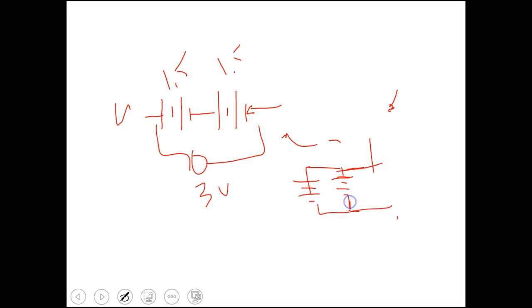Now what's this going to do? It's going to increase the current. So if we hook DC sources - you'll see your remotes do that more often - they'll hook them in series to get the voltage up, because with the voltage up, less current is required to produce the power. Sometimes though, we actually need current, so when you can't have extremely low current devices, your batteries will be hooked in parallel.